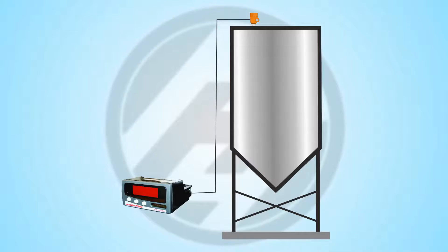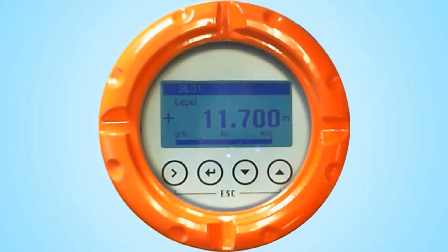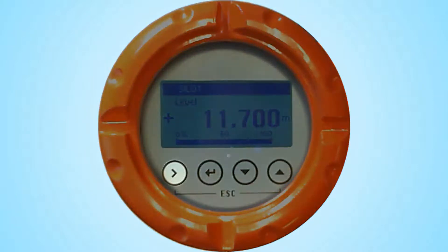We will cover programming of the high control digital displays in a later video. Before programming the unit, take a moment to familiarize yourself with the display keypad buttons. These require a magnetic pen to use, or you can remove the lid with the special tool provided and press the buttons. The right arrow key enters program mode submenus and moves the cursor to the next digit. The return key confirms changes and exits the current menu. The up and down arrows change the display screen in run mode and increase or decrease the value in program mode.